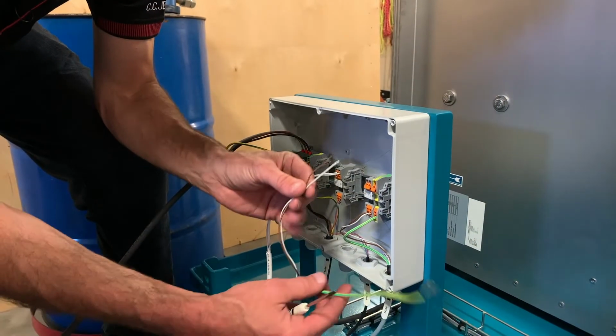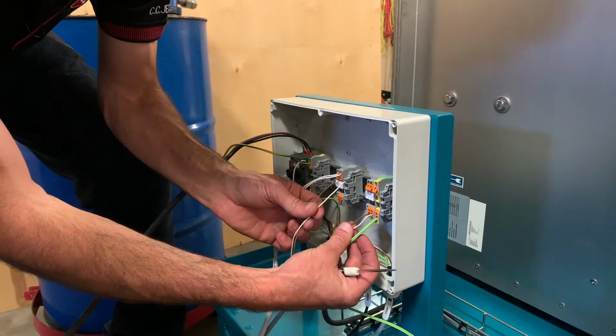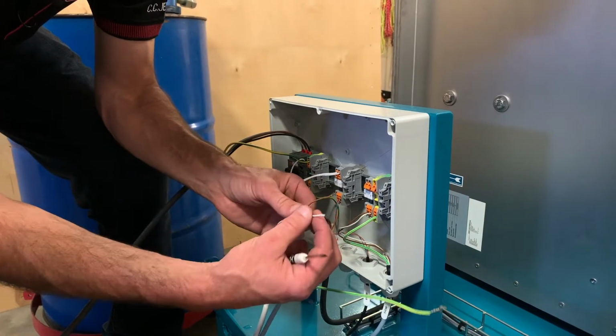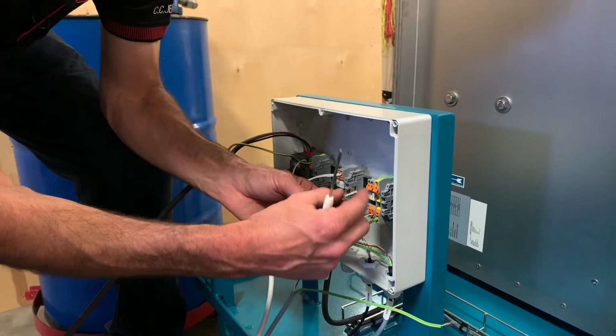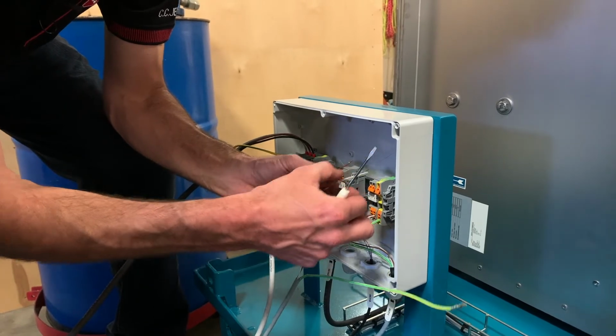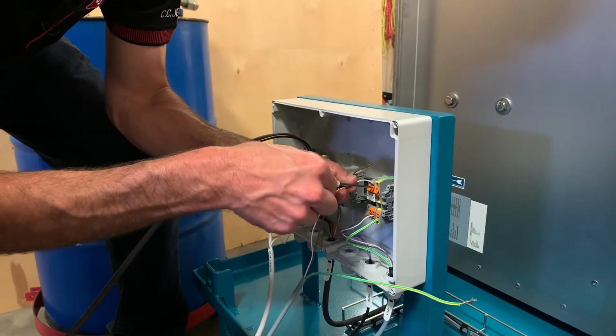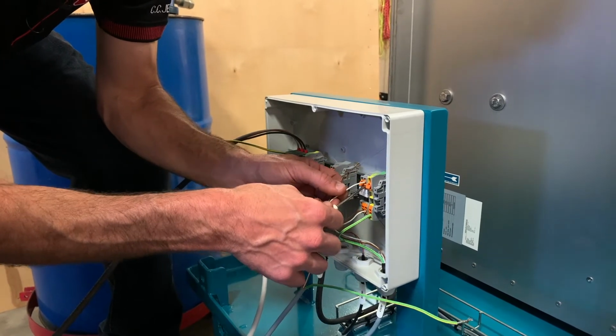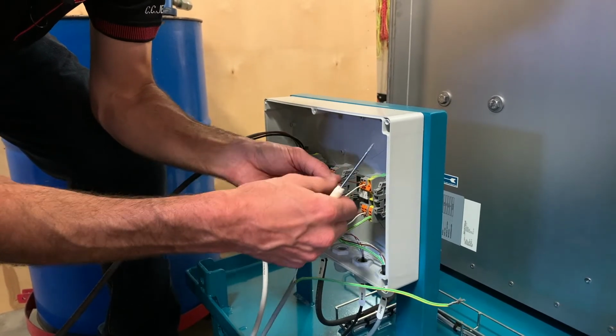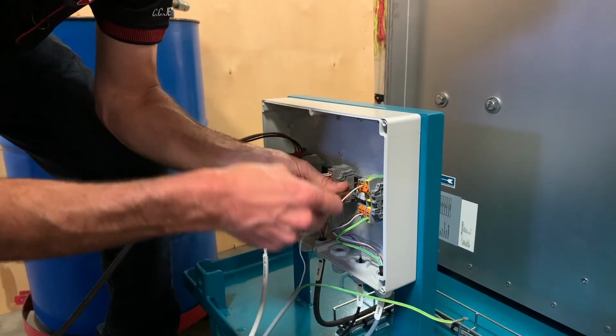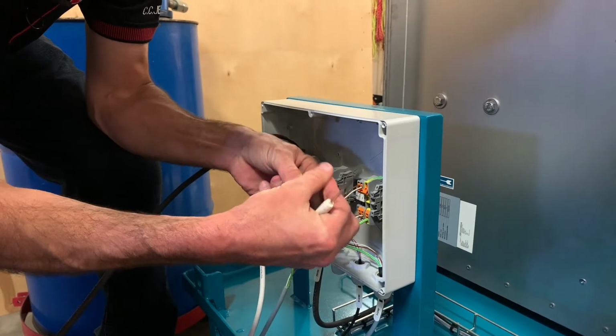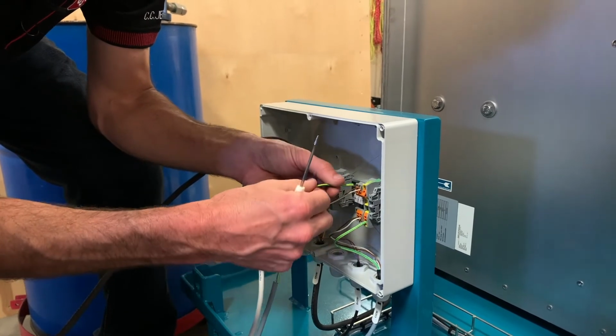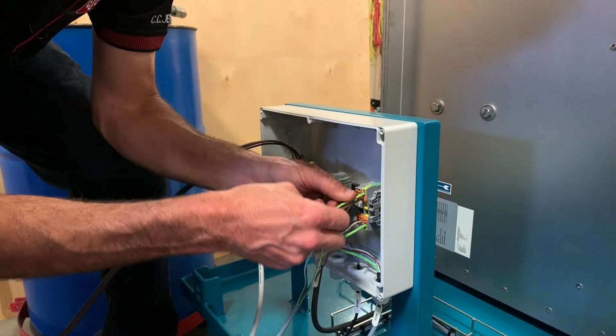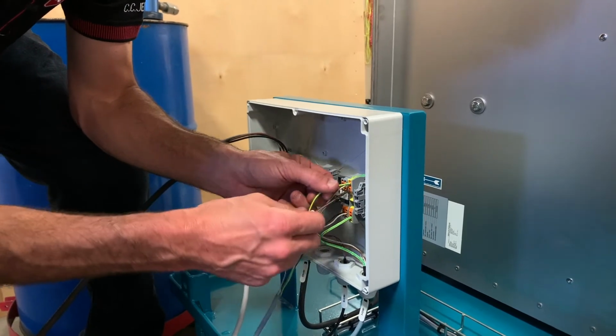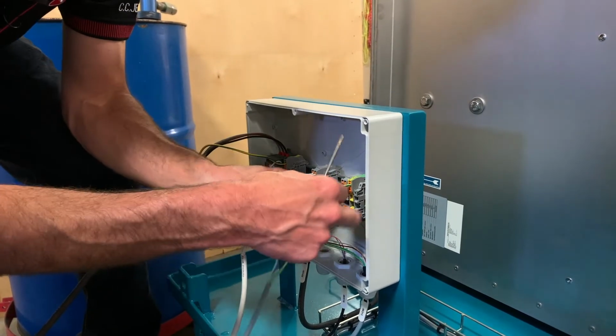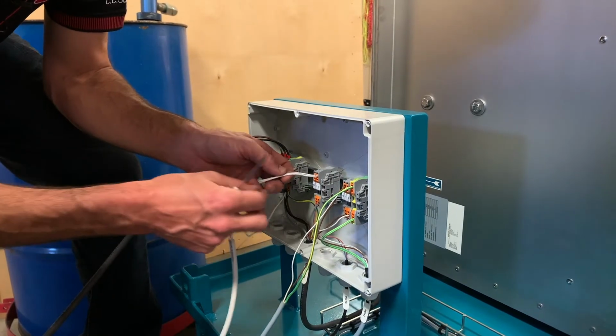The wires on the first cable correspond to the colors of the wires on the terminal blocks here. These wires do not need to be stripped. They just have to have cut ends, and slide them into the hole with a small screwdriver. Just tip it down, and that slices through the insulation to make the contact. So do that with each of these two, and same with the ground wire. The ground wire doesn't matter if it's stripped or not. Just insert it in, slide it down, locks it in. Just make sure that they're all flat with the surface, and carry on with the other wires.